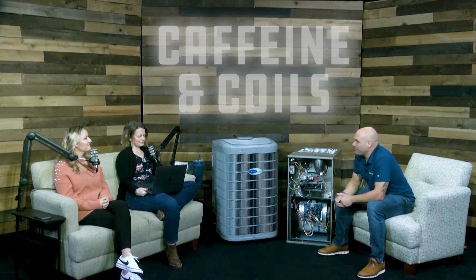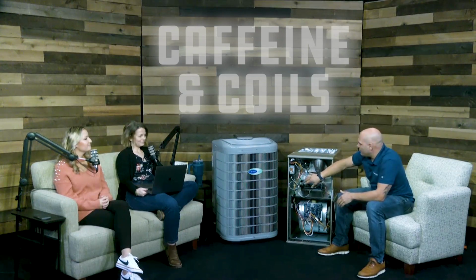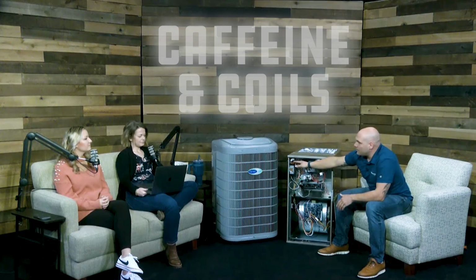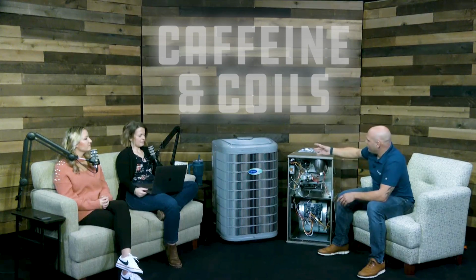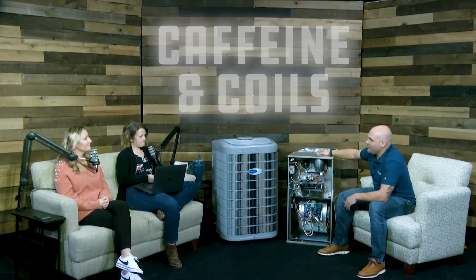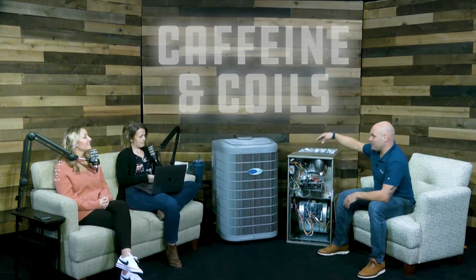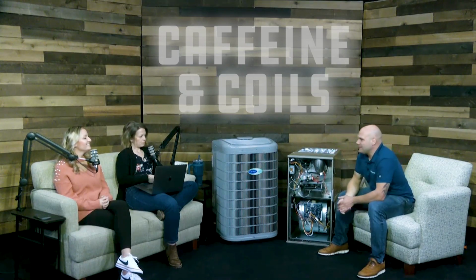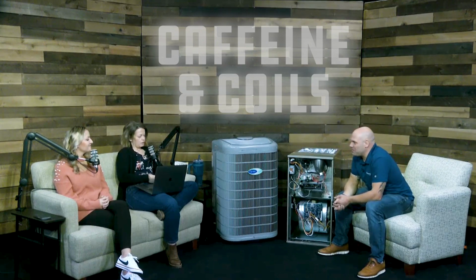Okay. Yeah. If you've checked everything out, if you're stuck on step 1, where you're getting a code 33 and you're going through your heat sequence, and you think the pressure switch is bad, but it's actually working, and you can test that with your meter, then pull the flue vent off and see if it works. But yeah, I mean, long term, this is where gas is venting, right? So you don't want that to be off. But yeah, I think that would be the most memorable. Do you have any other furnace tips or information you want to share with us?